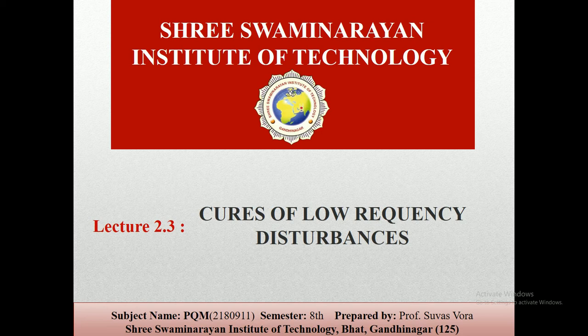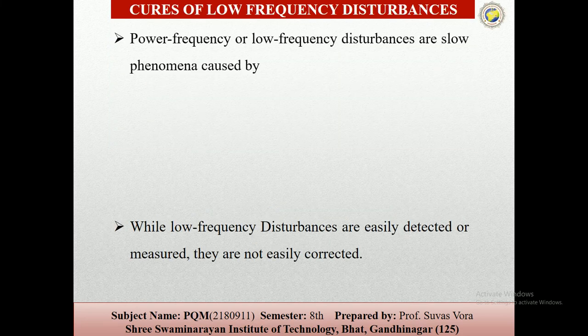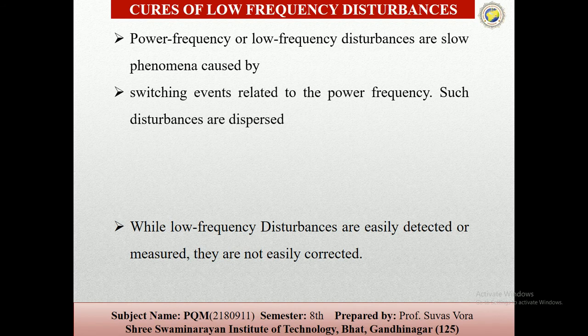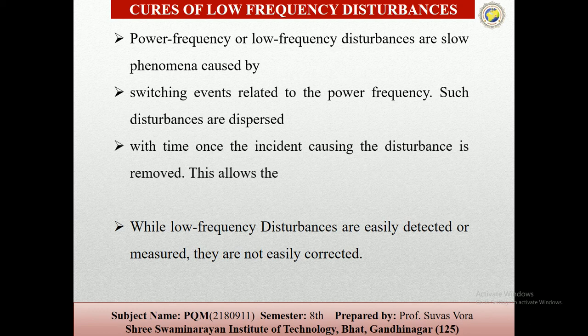So if the low frequency disturbance arises at that time, what happens? The power frequency or low frequency disturbances are slow phenomena caused by switching events related to the power frequency. Once the initiating cause of the disturbance is removed, the disturbance dissipates over time, which allows the power system to return to normal operation.